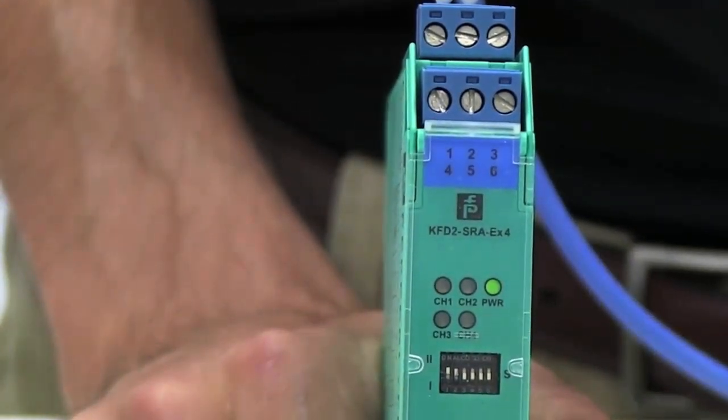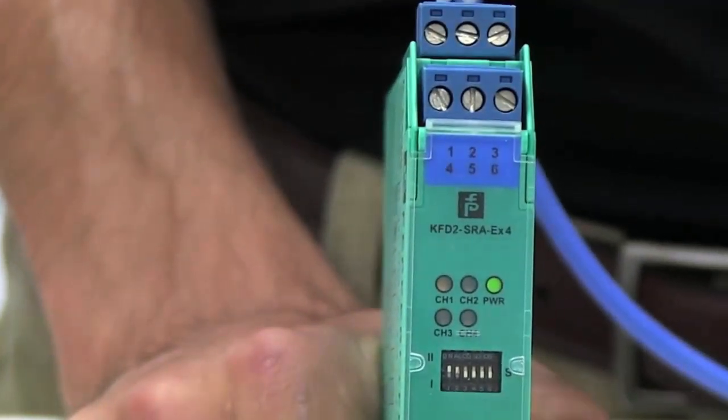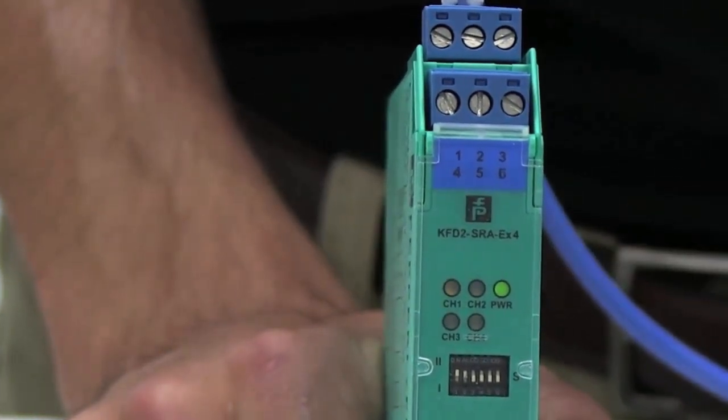If normally open logic is desired, DIP switches on the front of the barrier can be inverted to send a normally open signal to a control device, have it be a PLC, located back in the safe area.